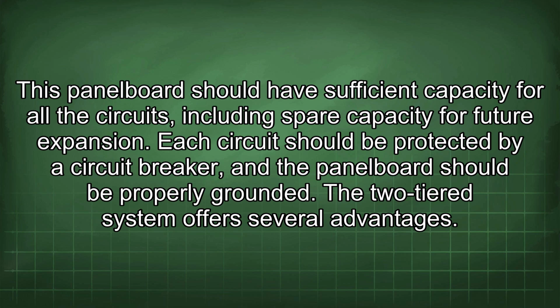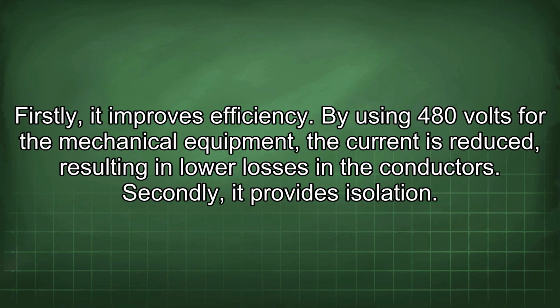Each circuit should be protected by a circuit breaker, and the panel board should be properly grounded. The two-tiered system offers several advantages. Firstly, it improves efficiency. By using 480 volts for the mechanical equipment, the current is reduced, resulting in low losses in the conductors. Secondly, it provides isolation.